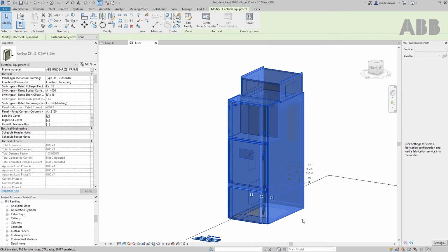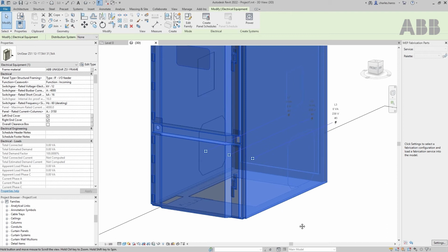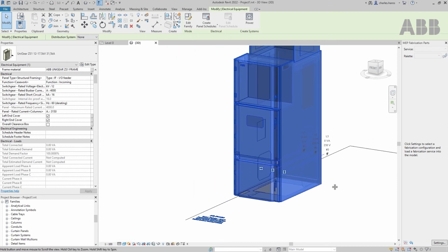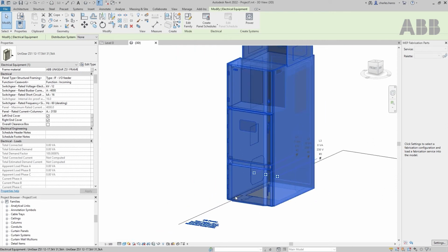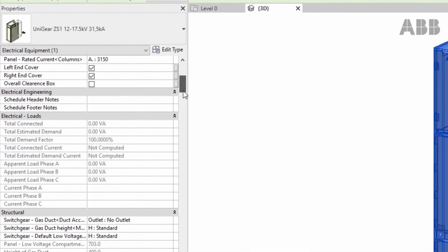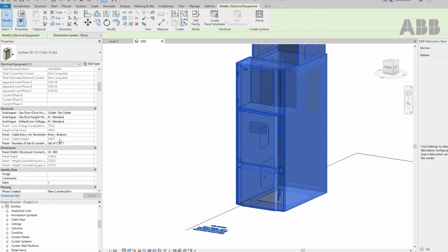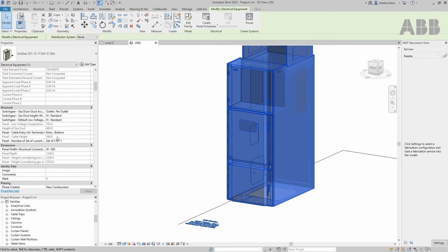The BIM of this panel includes the connection cables, presented by the three blue dots in the lower compartment. This information can help you measure the cable length from the medium voltage endpoint in your building to the switchgear connectors. For a more precise measurement, the Properties section can give you the exact length of the cable needed inside the cubicle, from the bottom to the connector.